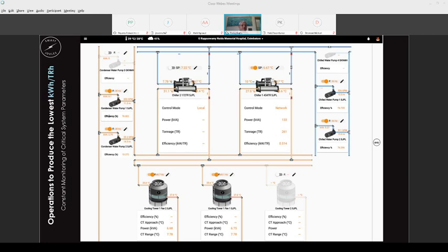In this slide, you're seeing those equipment at the bottom - those are the cooling towers. If you're observant and go on the roof, you will see a lot of big towers evaporating water, providing evaporative cooling. What it does is provide heat transfer between the refrigerant, or the condenser of the refrigerant, and the water, which is evaporated using four fans. So it's using the wet bulb temperature of air to bring down the temperature of the water.